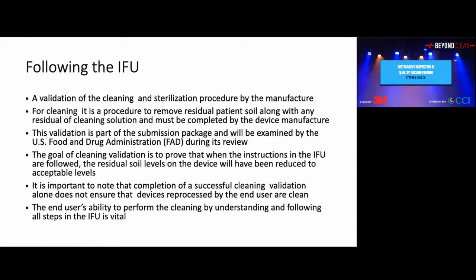Validation of the cleaning and sterilization procedure by the manufacturer. That manufacturer, that orthopedic set or whatever, they're the ones who actually did all the validation on cleaning and sterilization. And I know some people might not want to hear this, even though washer companies say they put an orthopedic set through for this and this time, you still need to refer back to the manufacturer of that orthopedic set and break it down and do it their time. It might say minimum, but if they say minimum of 6 minutes, that's the minimum you need to do, not something else, because they've done the validation.